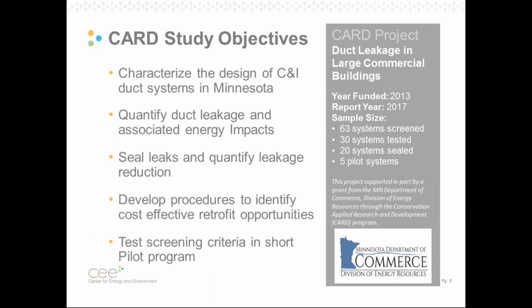We essentially started from scratch when we were trying to understand whether retrofit duct sealing can be a savings measure. And what that meant was we first needed to characterize what kinds of duct systems are found in commercial institutional buildings in Minnesota. And from that we moved on to quantifying duct leakage. We measured duct leakage and tried to estimate its energy impacts. Following that, we decided to try out retrofit duct sealing.